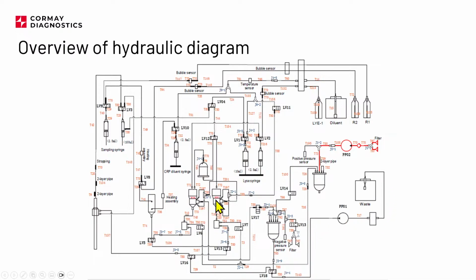The same thing is happening on the RBC. Bottom port, this part, this part, this part, pump and waste container. The other part here, the top part, when you trace the connections, it's going here. So it's supplying the same function, and it's going here, positive pressure. So this is a tank which is storing a little bit of positive pressure, since this pump is making this positive pressure. And this tank is used to generate air bubbles during the mixing process in the chamber.